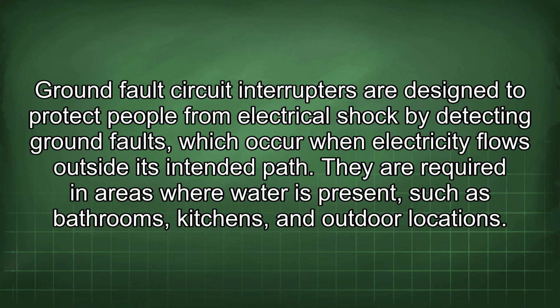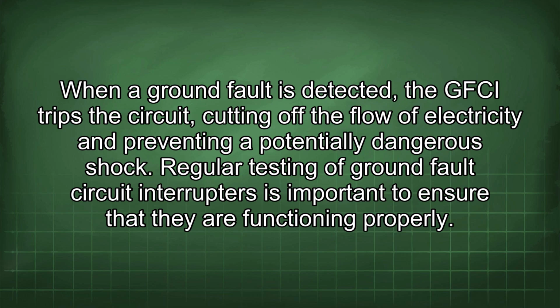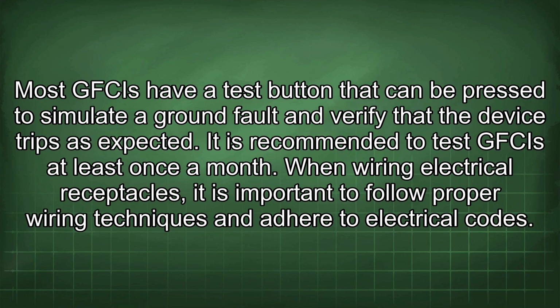Ground fault circuit interrupters are designed to protect people from electrical shock by detecting ground faults, which occur when electricity flows outside its intended path. They are required in areas where water is present, such as bathrooms, kitchens, and outdoor locations. When a ground fault is detected, the GFCI trips the circuit, cutting off the flow of electricity and preventing a potentially dangerous shock. Regular testing of ground fault circuit interrupters is important to ensure that they are functioning properly. Most GFCIs have a test button that can be pressed to simulate a ground fault and verify that the device trips as expected. It is recommended to test GFCIs at least once a month.